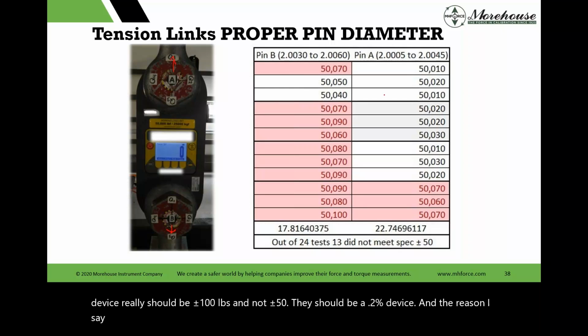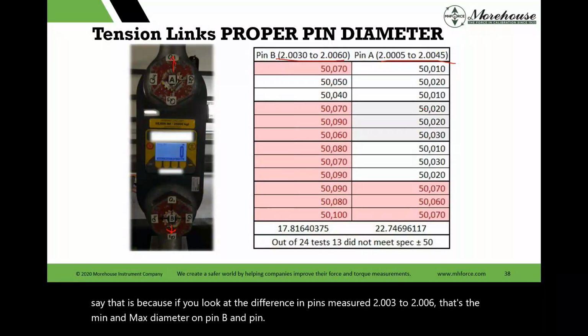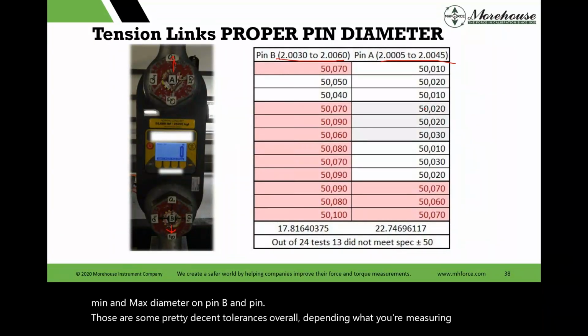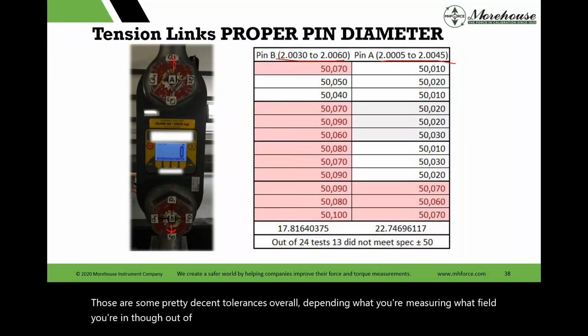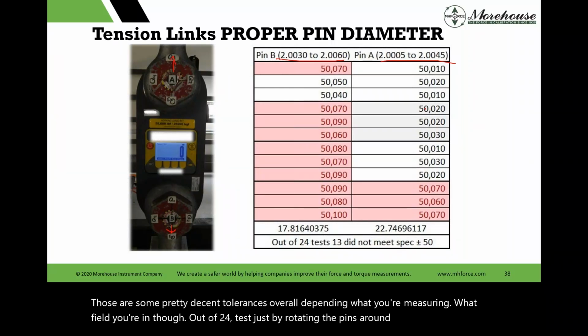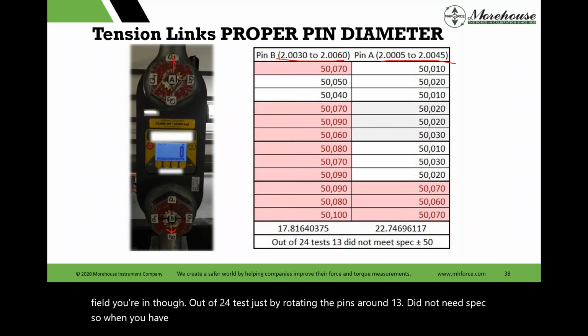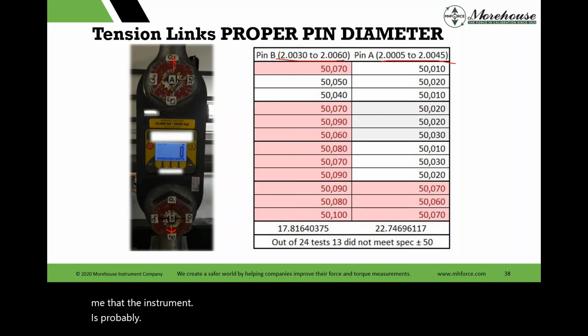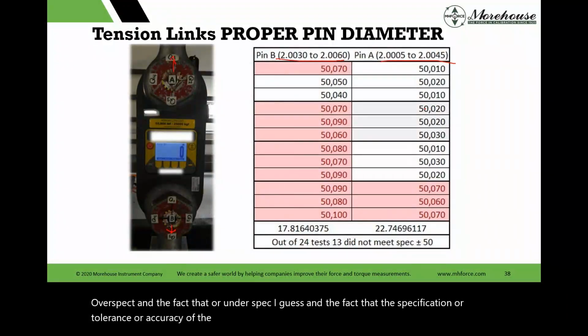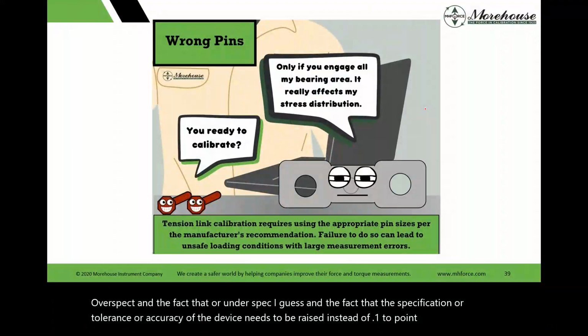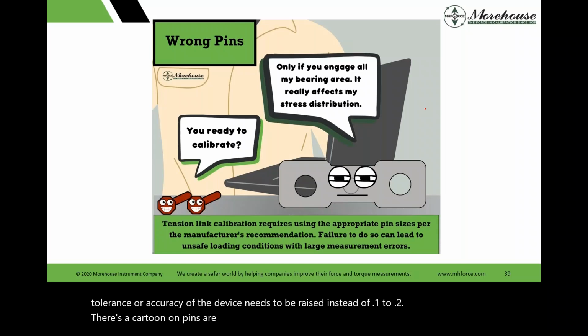And the reason I say that is because if you look at the difference in pins measured, 2.003 to 2.006, that's the min and max diameter on pin B and pin A, those are some pretty decent tolerances overall, depending on what you're measuring, what field you're in. Though out of 24 tests, just by rotating the pins around, 13 did not meet spec. So when you have that type of issue, just rotating pins, not even the size of the pin, it's telling me that the instrument is probably underspec'd, and the tolerance or accuracy of the device needs to be raised from 0.1 to 0.2. There's a cartoon on pins. You ready to calibrate? It affects.